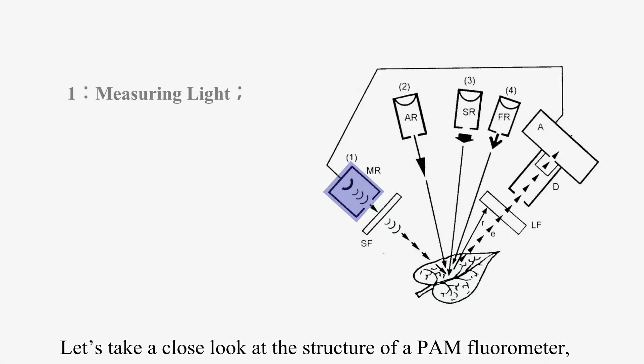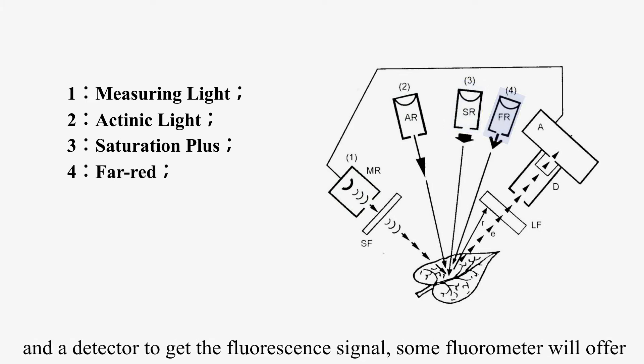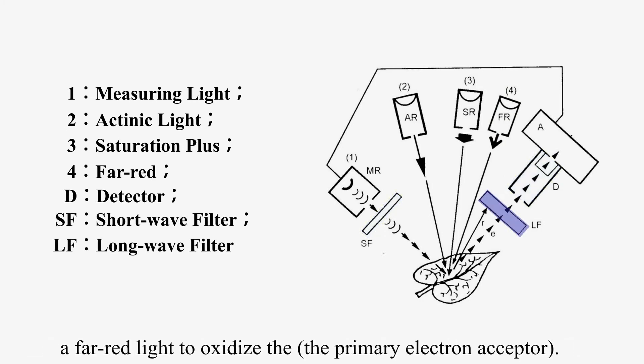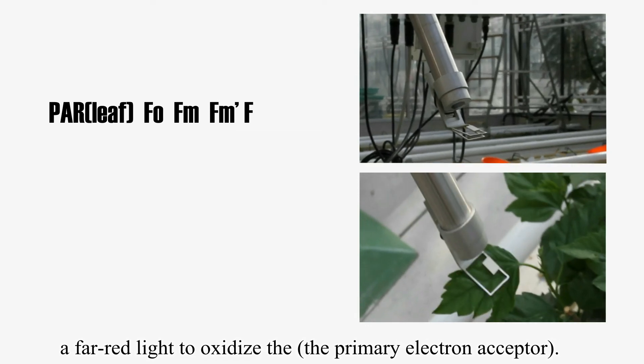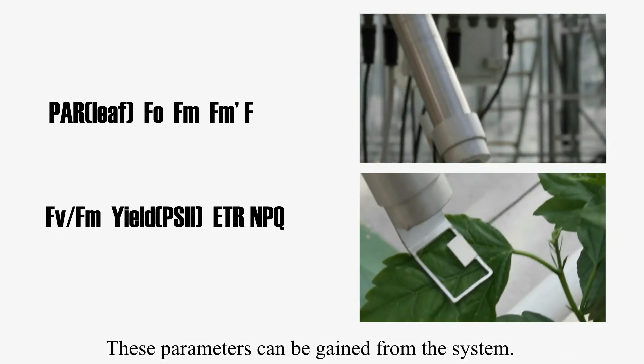Let's take a close look at the structure of a PAM fluorometer. Basically, it includes measuring light, actinic light, saturation pulse, and a detector to get fluorescence signal. Some fluorometers will offer far red light to oxidize the primary electron acceptor. These parameters can be gained from the system.